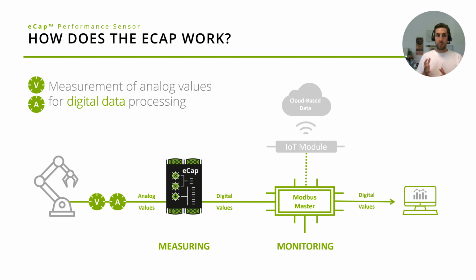And now usually the Modbus master would take over the monitoring part, while the eCap sensor will do the measuring part, and you can process those values through this very universal Modbus RTU framework to either send it to an IoT module and upload it into a cloud, or process it on site with your PLC or local control system.